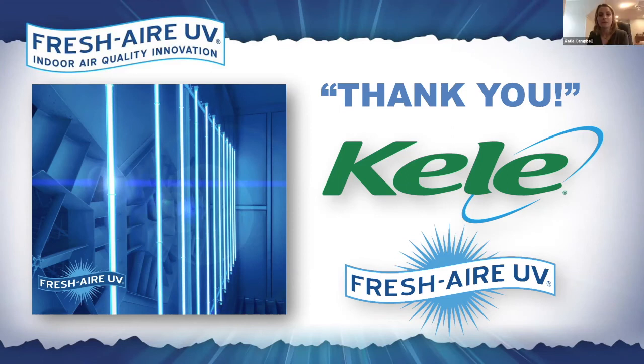Gotcha. Great information. Benjamin asked, what components in a duct or AHU are most susceptible to degradation due to UVC lighting? Are special UV-resistant coil coatings required? No. So, you know, back in the day, we used to say, plastic drain pans, especially on the residential side, to shield them and put aluminum. And then it really became a non-issue.